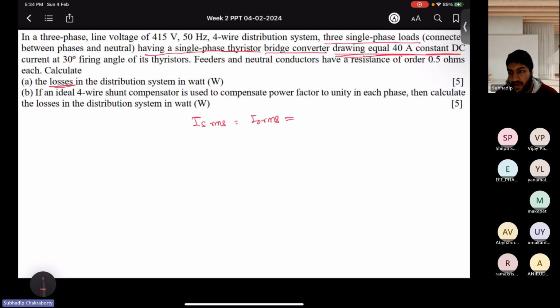So loss is active power loss only. Active power loss is I RMS square into R. Whatever signal is flowing in the lines, the RMS value of that current signal, squared and multiplied by R, is the total loss in the distribution system. Since this is 3-phase, you have 3 such phases, so 3 times, and this is a 4-wire distribution system. Since 4 wires are there, 4 feeders are there. So what will be the total loss, P loss?